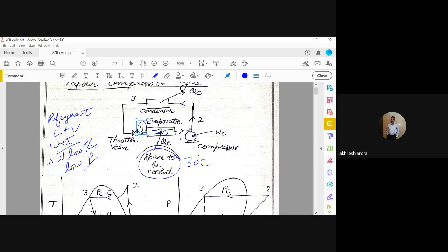The refrigerant going to the atmosphere may cause harmful effects like ozone depletion, or global warming, or other effects which we may not know today. So our purpose is to reuse this refrigerant which has been converted from liquid to vapor. How has it been converted? By the addition of heat, and this heat is basically latent heat. If we throw away this latent heat which it has taken, then we can bring it back to its original state, state point number 4, at low temperature and low pressure.